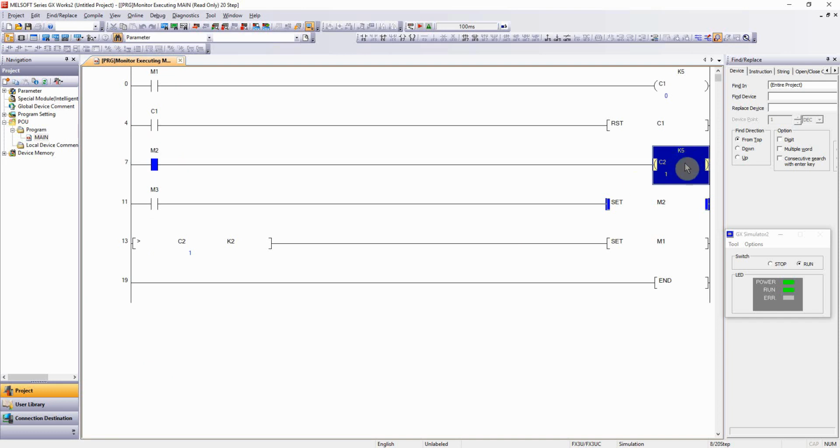In most PLCs, this counter would be just going up, up, up, up, up. It'd be constantly counting for each scan that the PLC does, because this contact's on, so it's counting. In this case, it's not doing that, but I'd still advise that on all counters you use rising edge contact. It's just a safer way to play.